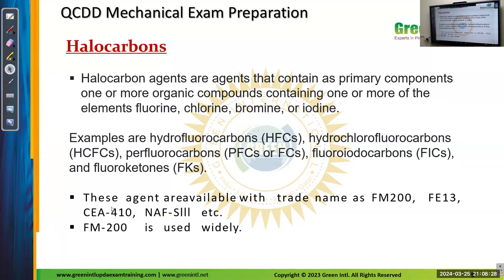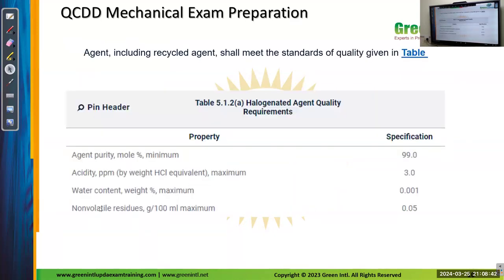These agents are available under the trade names FM200, FE13, CEA-410, NAF S3, etc. FM200 is a widely used type of halocarbon. So a halogen agent must contain a minimum of 99% agent purity, with acidity having a maximum of 3 ppm. Water content will be 0.